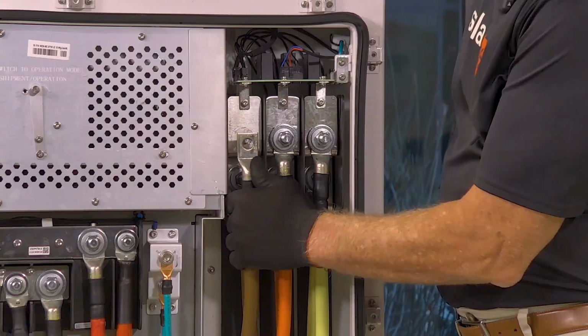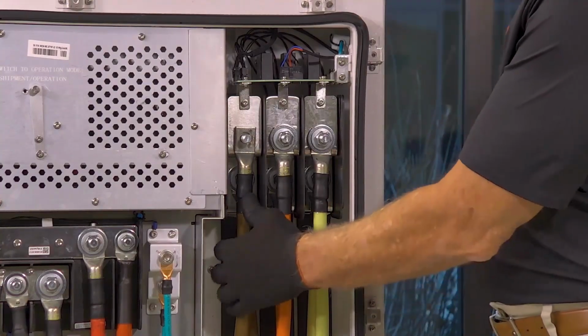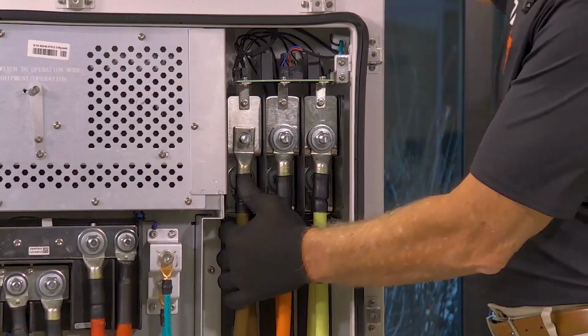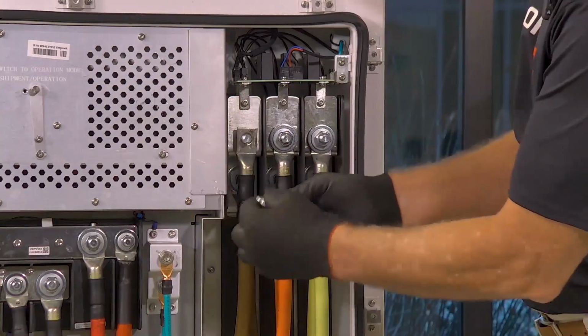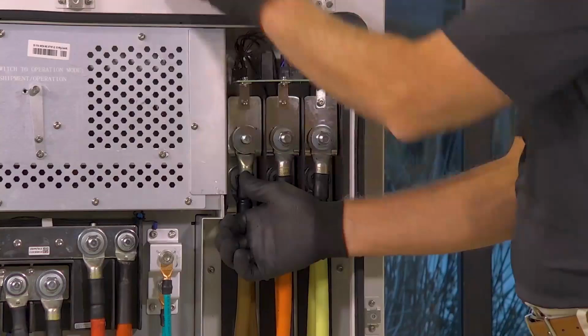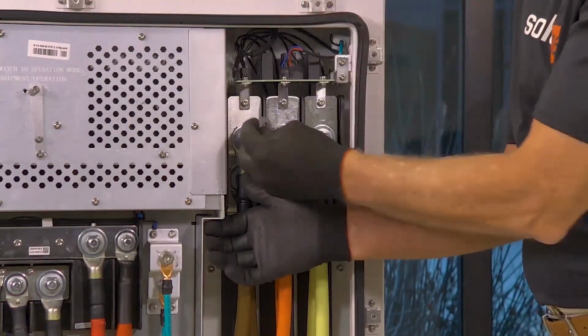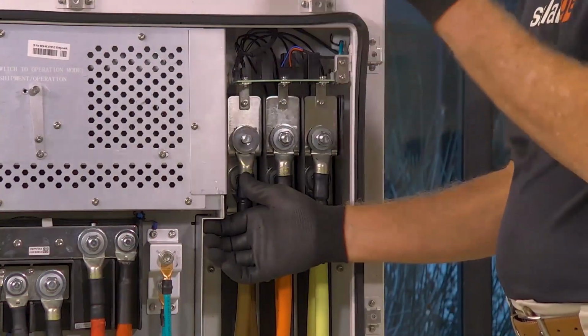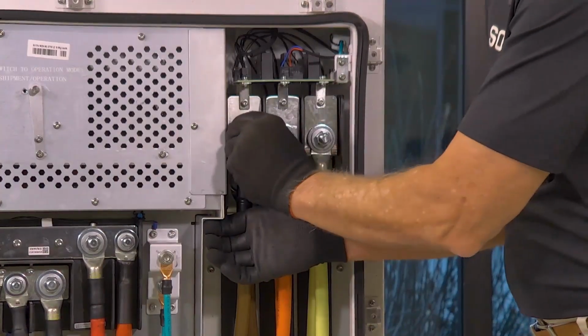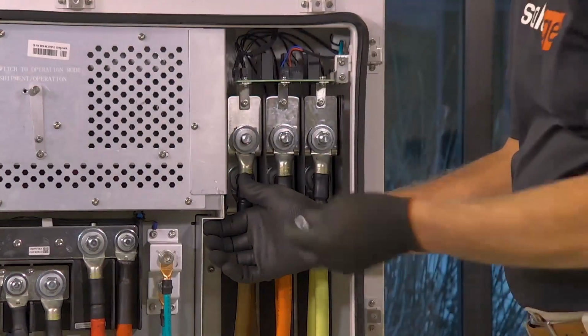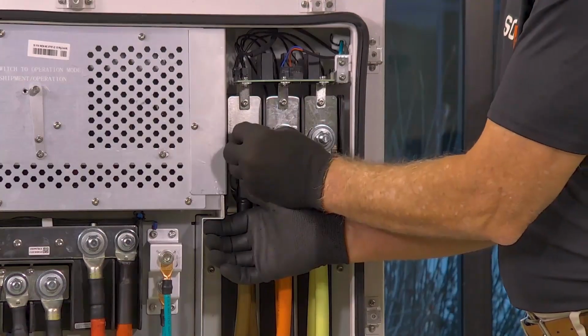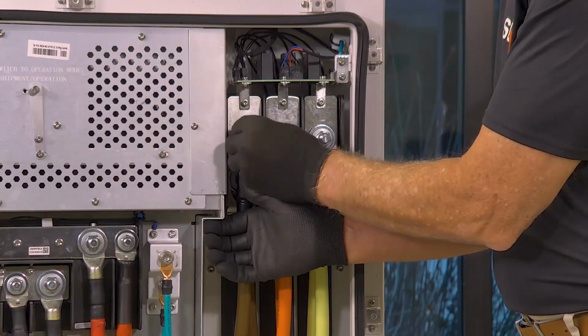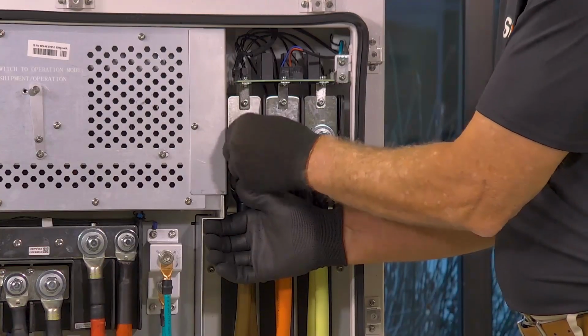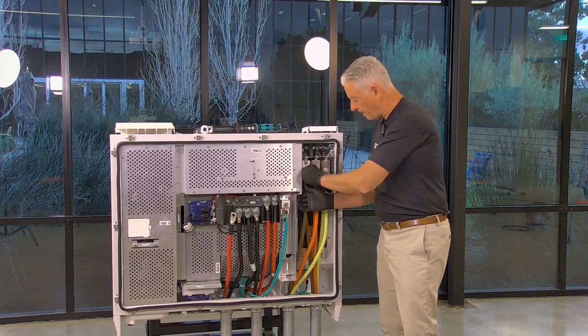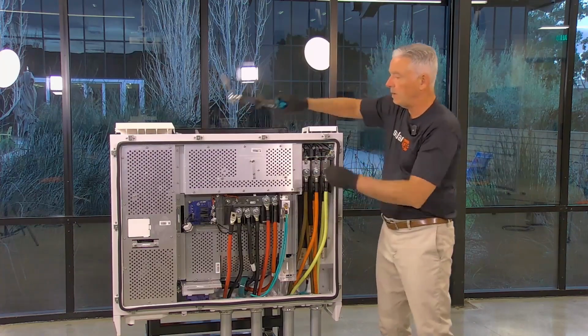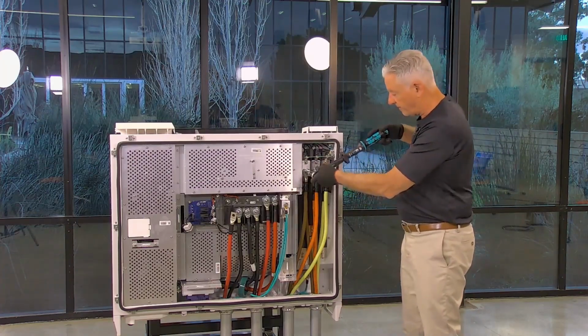You land the conductor on the threaded stud. You seat the compression lug on the terminal. Then you put in your first washer, flat washer, then the Belleville washer, and you have to make sure you put it on properly because it's directional. And then you put on your 18 millimeter bolt or nut. Then we torque it down to 310 inch-pounds.